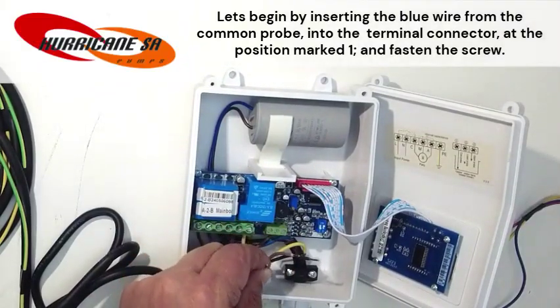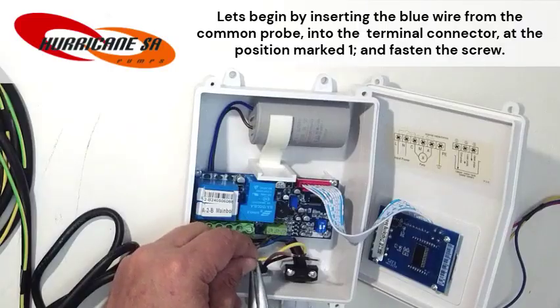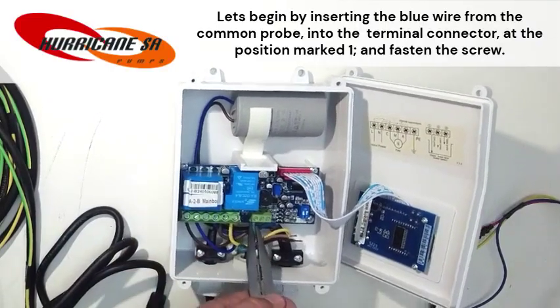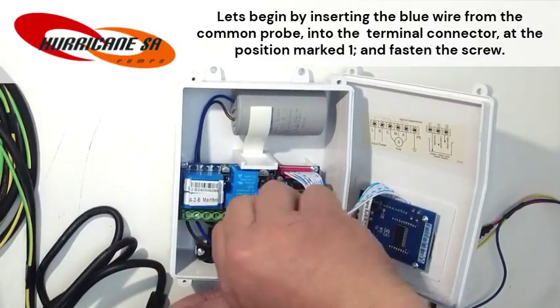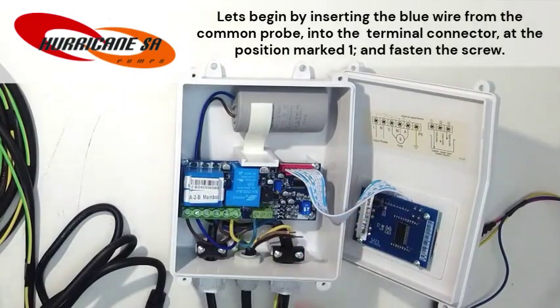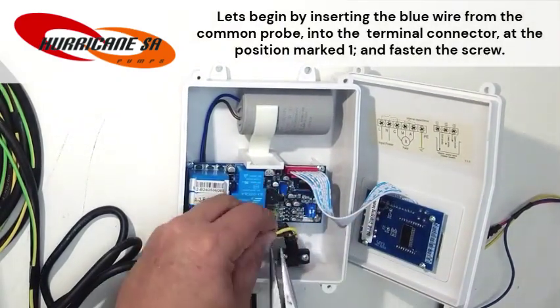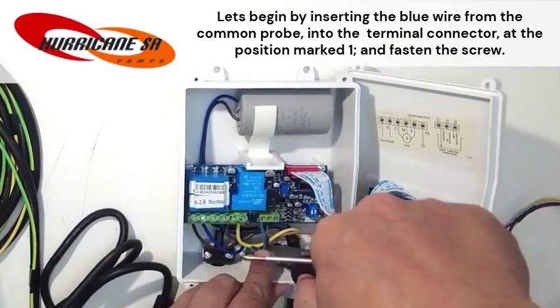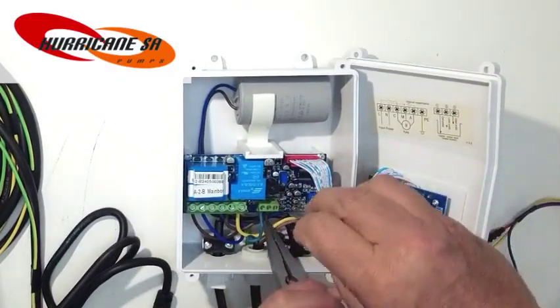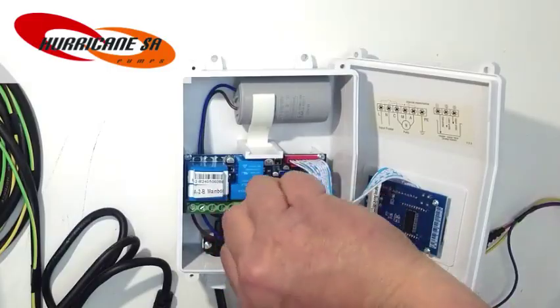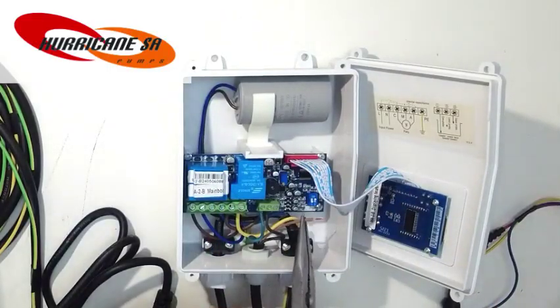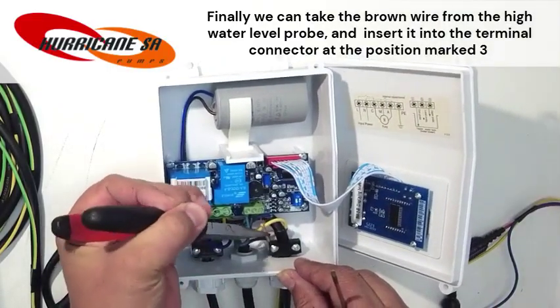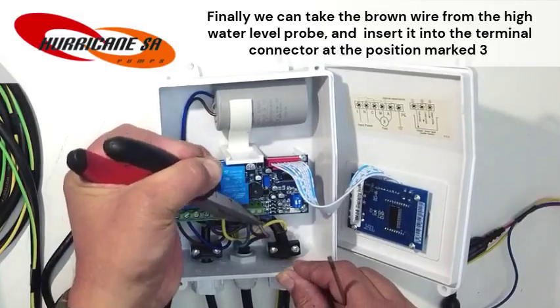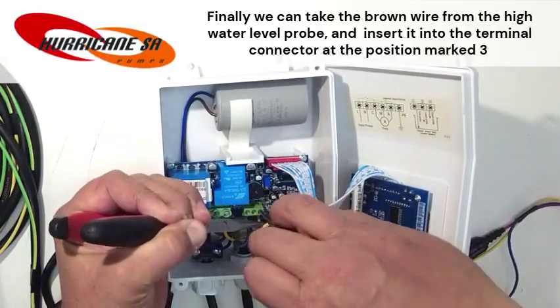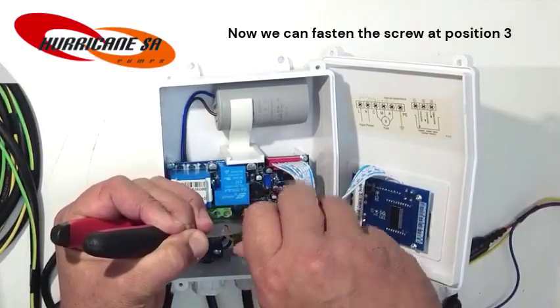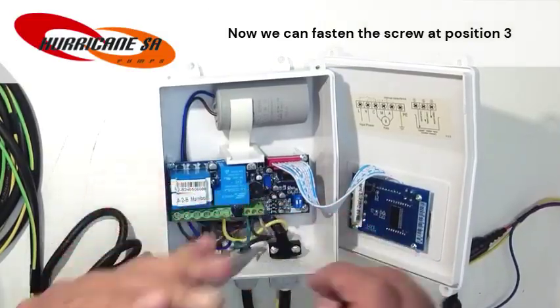Let's begin by inserting the blue wire from the common probe into the terminal connector at the position marked 1 and fasten the screw. Next, we can insert the black wire or the low level probe wire into the terminal connector at the position marked 2. Then we can fasten the screw. Finally, we can take the brown wire from the high water level probe and insert it into the terminal connector at the position marked 3. Now we can fasten the screw at position 3.